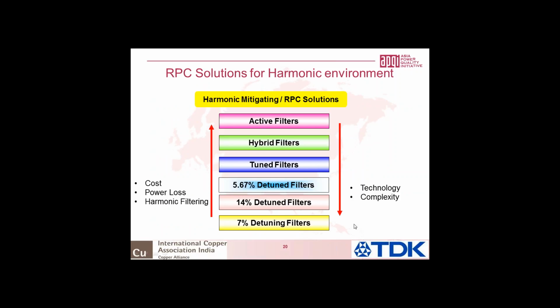So maybe I would skip this. This only shows various series reactors which are used for partial tuning or detuning, and the various tuned frequencies at a fundamental of 50 hertz. And this is a generic guideline. Whenever there are general rules, I would say people should use them with caution, because these are generic. You could have a specific case where this may or may not work. So this is what I generally use.